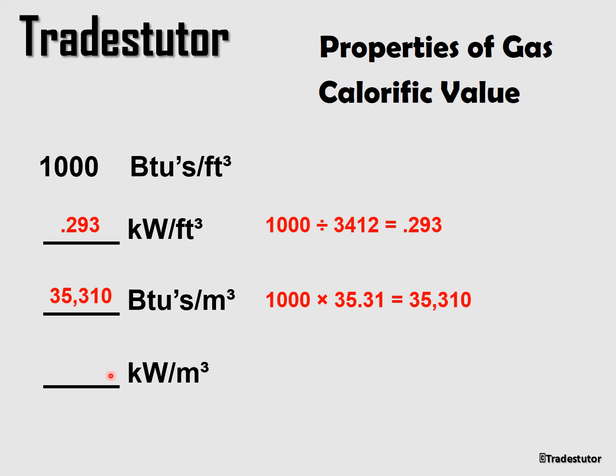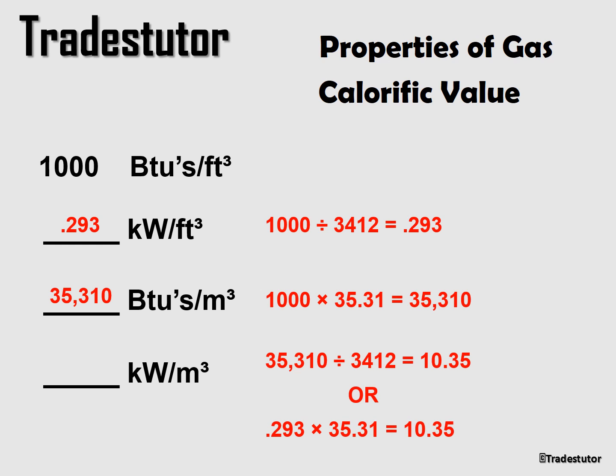For the fourth value — kilowatts per cubic meter — we can do it two ways. We can go from kilowatts per cubic foot and multiply by 35.31 to convert to kilowatts per cubic meter, or we can go from BTUs per cubic meter and divide by 3412 to get kilowatts per cubic meter. Either path works, giving us our final converted calorific value.